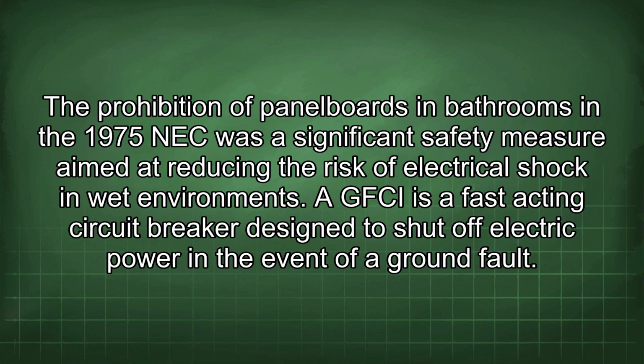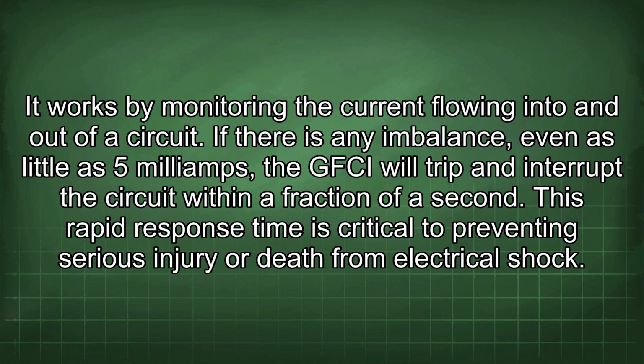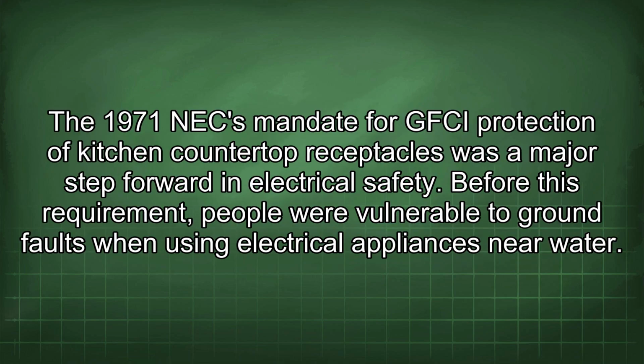A GFCI is a fast-acting circuit breaker designed to shut off electric power in the event of a ground fault. It works by monitoring the current flowing into and out of a circuit. If there is any imbalance, even as little as 5 milliamps, the GFCI will trip and interrupt the circuit within a fraction of a second. This rapid response time is critical to preventing serious injury or death from electrical shock. The 1971 NEC mandate for GFCI protection of kitchen countertop receptacles was a major step forward in electrical safety. Before this requirement, people were vulnerable to ground faults when using electrical appliances near water.